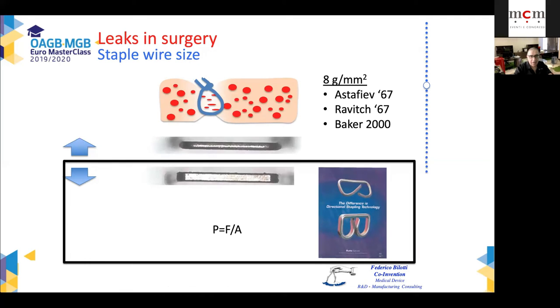Now, a manufacturer on the market decided to change the shape of the staples and flatten their surface. By flattening the surface, the pressure applied on the tissue changes. Because of the simple formula, pressure equals F over A, if A increases, the pressure decreases. So you don't apply 8 gram per millimeter square, but you apply a lesser pressure. And that's why the design of the staple with flattened surfaces is interesting, how it would keep its shape better than the rounded wire staple.